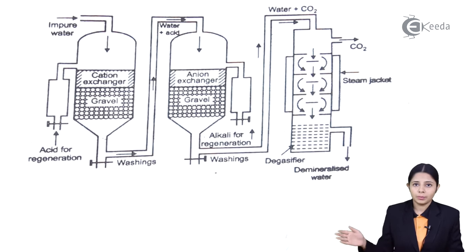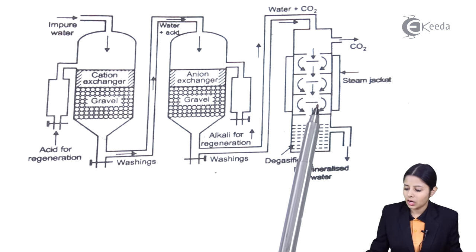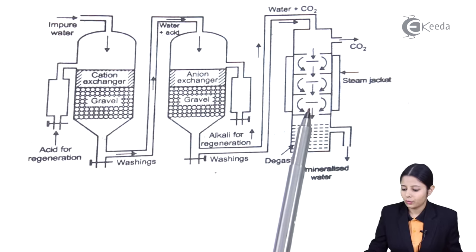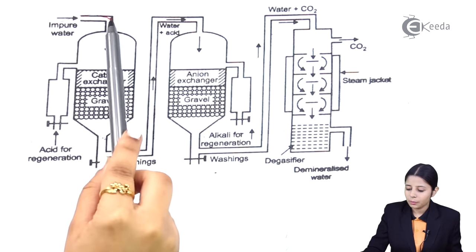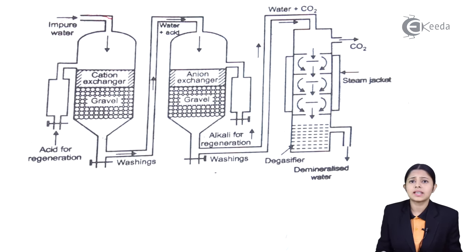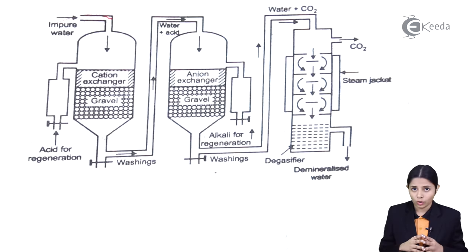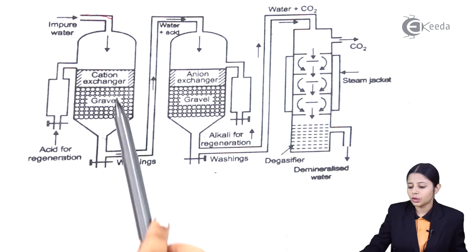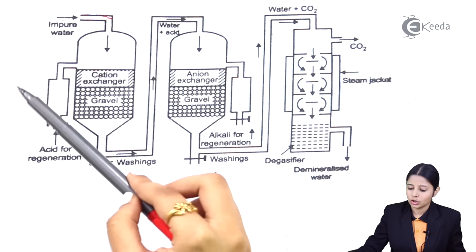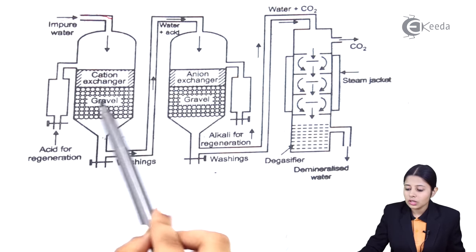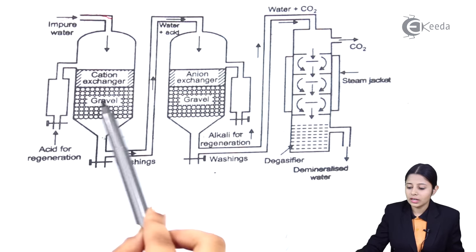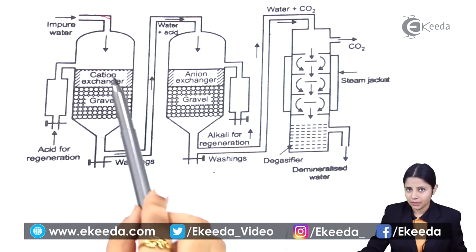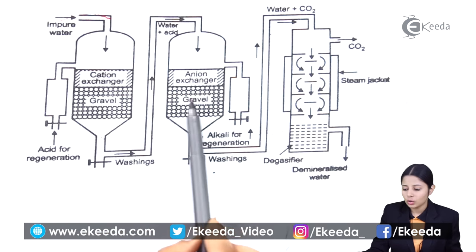Let us see the exact process with the help of a diagram. As explained, we have three towers: the first is the cation exchanger, the second is the anion exchanger, and the third is the de-gasifier. The impure water is first passed into the cation exchanger. Both towers contain gravel — gravel is added to slow down the flow of water, so the water doesn't flow directly from top to bottom but drips slowly, giving enough time for the cation and anion exchange reactions to take place properly.